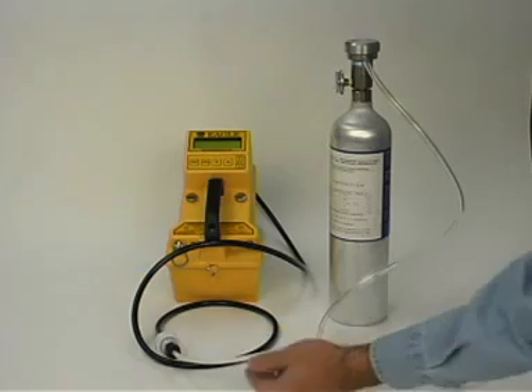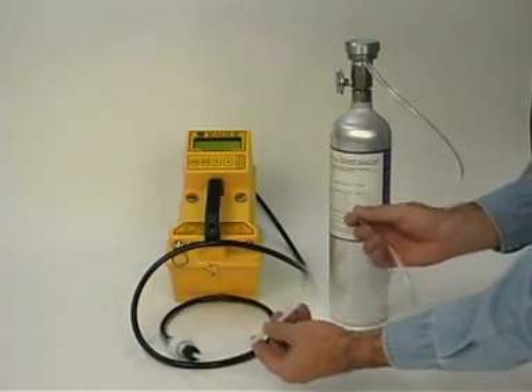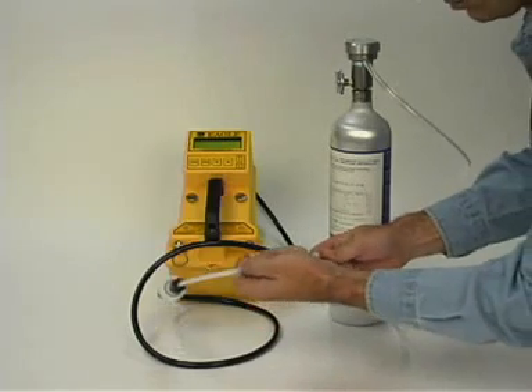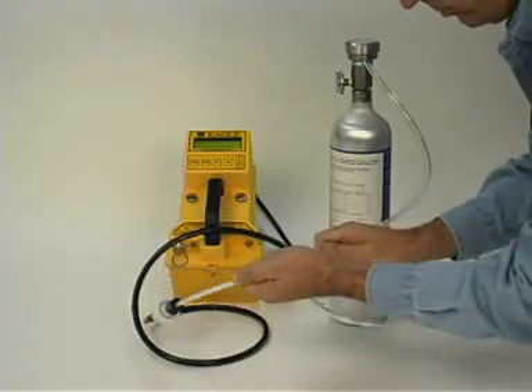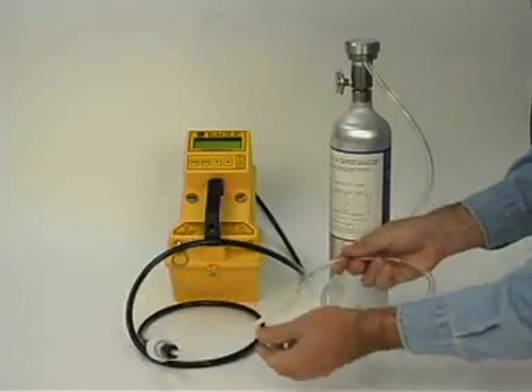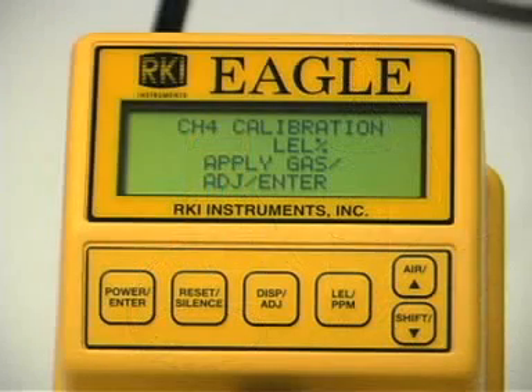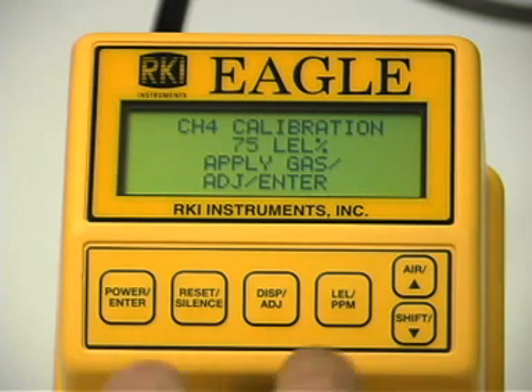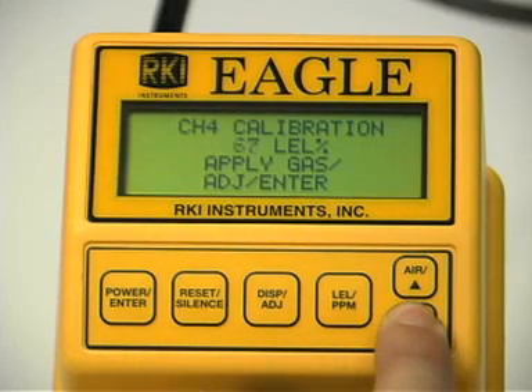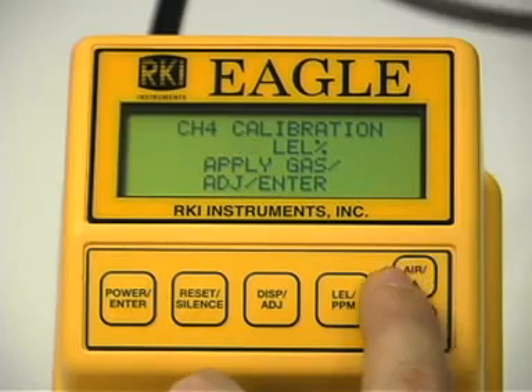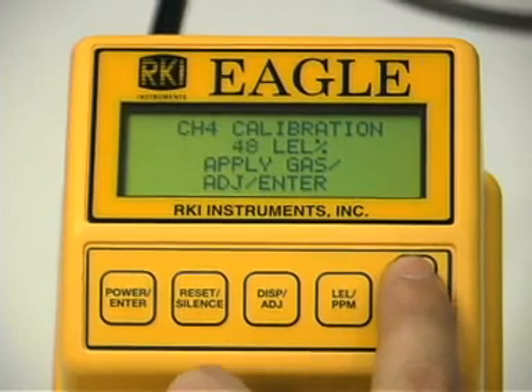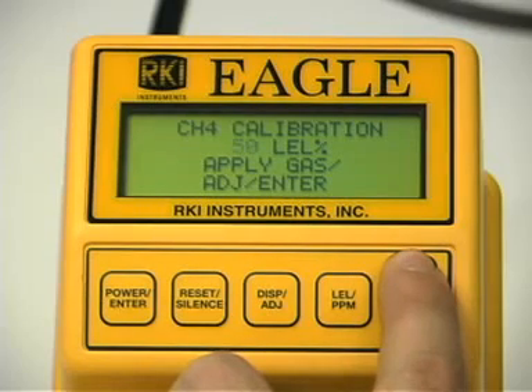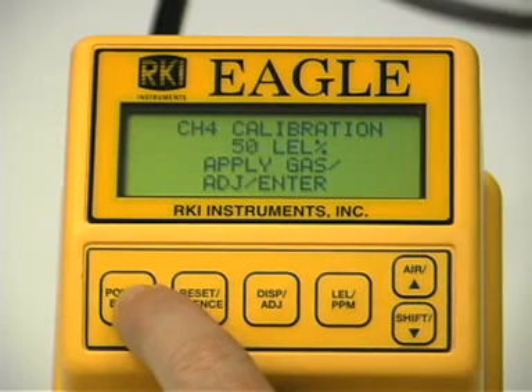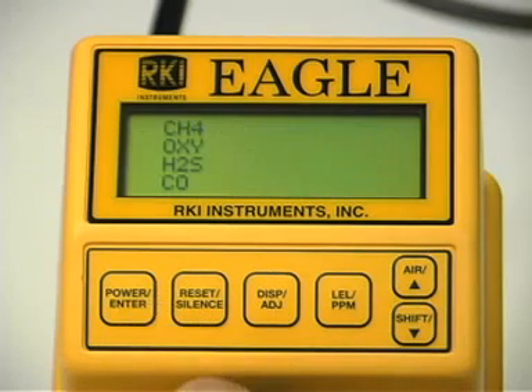Connect the tubing from the demand flow regulator to the Eagle's probe. The Eagle will immediately begin drawing in the calibration sample from the cylinder. Allow the reading on the Eagle's display to stabilize. If necessary, use the up and down buttons to adjust the reading to match the concentration listed on the calibration cylinder. Press the enter button to set the span value. Single calibration end will display, followed by the single calibration menu.